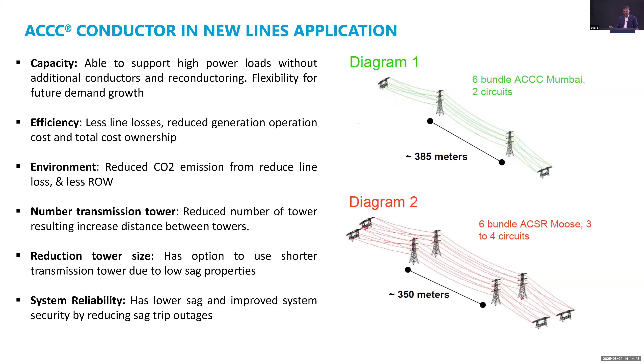projects. The other way HTLS conductors could be used is to reduce the number of transmission towers. This HTLS group of conductors have very low sag. In that sense, you can put the towers further apart. And if you can put towers further apart, you can reduce the number of towers for the overall project easily by 10 to 20%, right? This is one way you can use it. The other way is you can reduce the tower size, right? If you reduce the tower size, that means your right of way will be reduced, right? So this then reduces your land acquisition requirements.